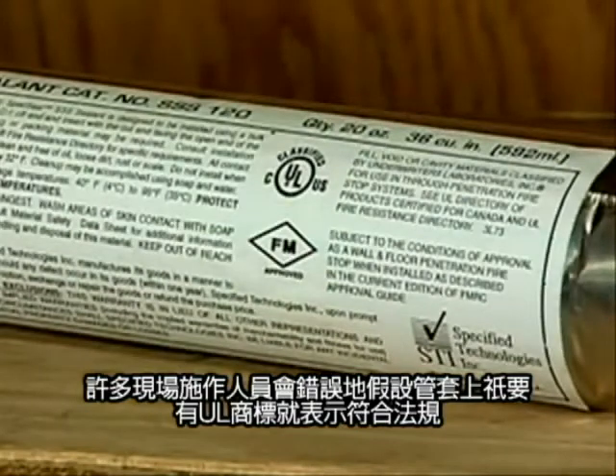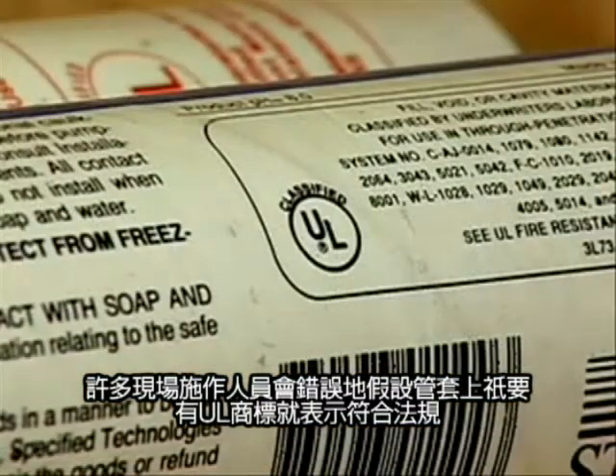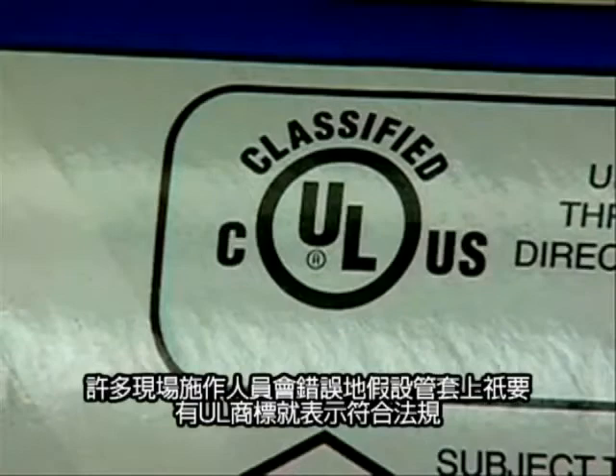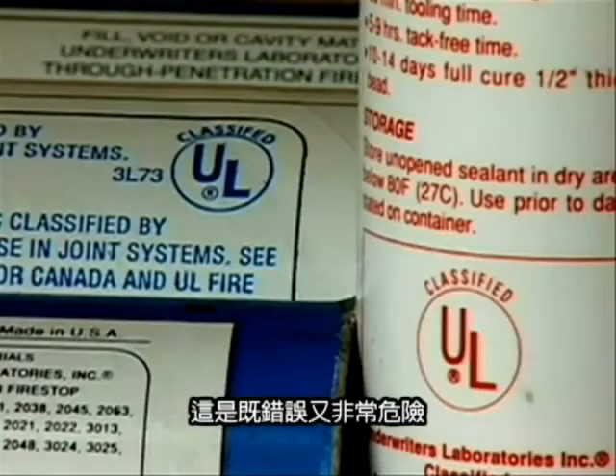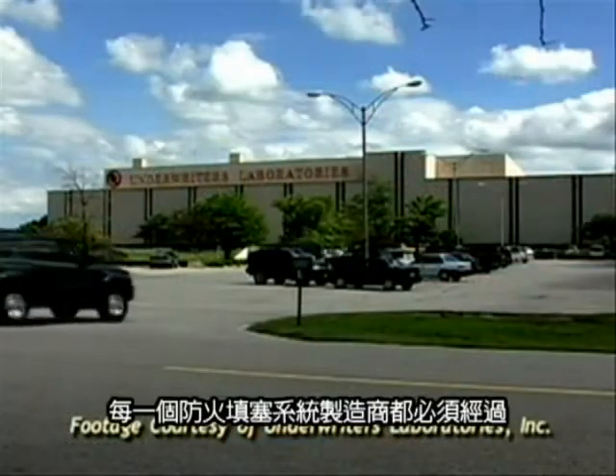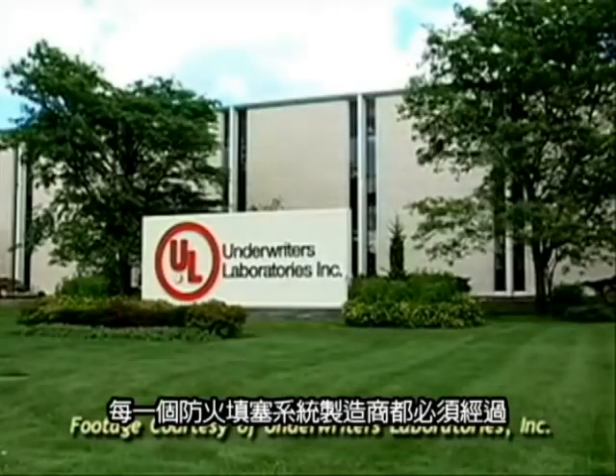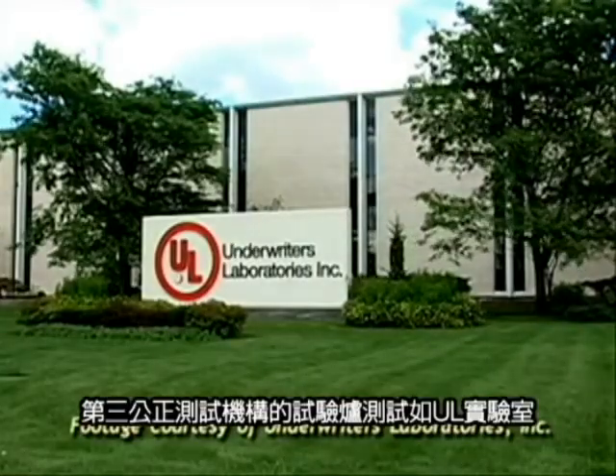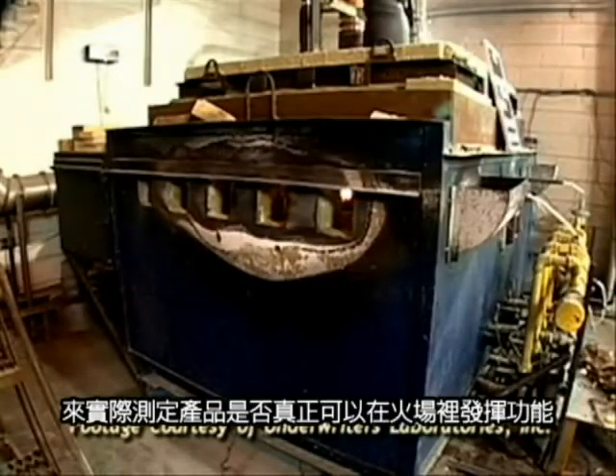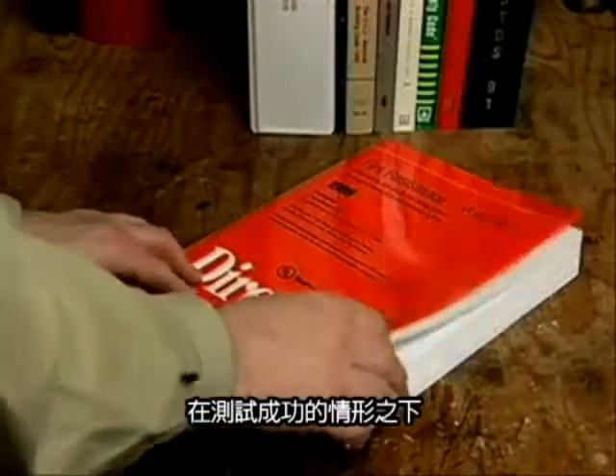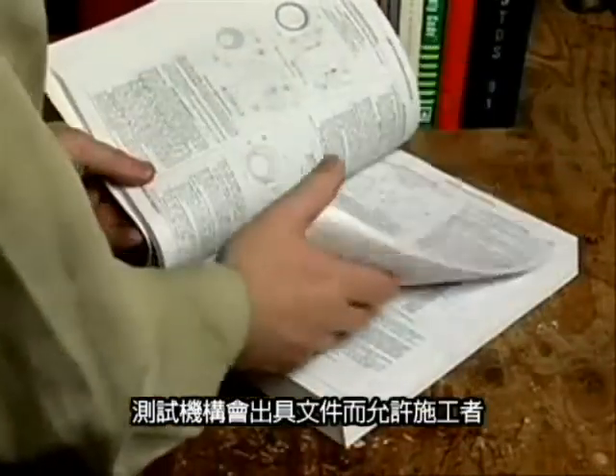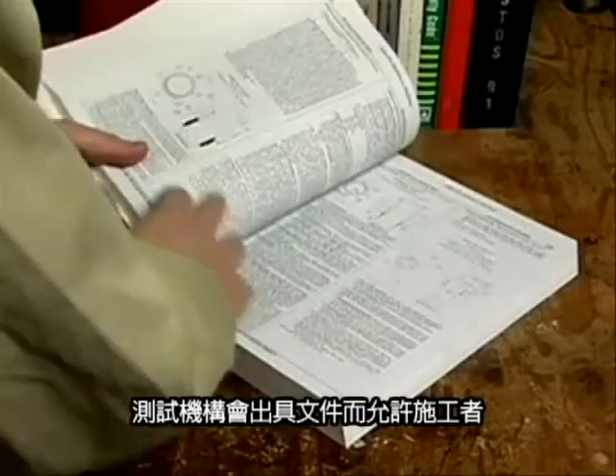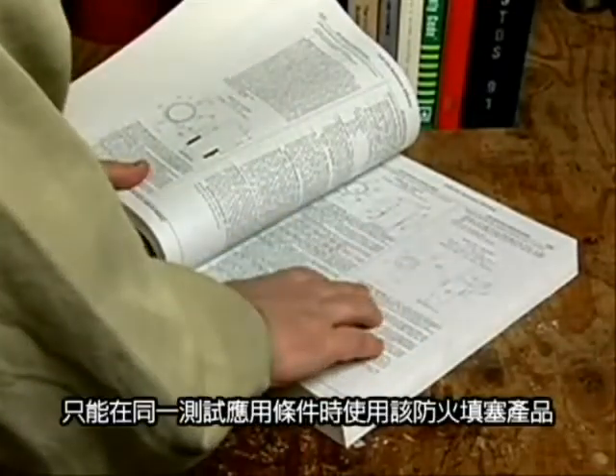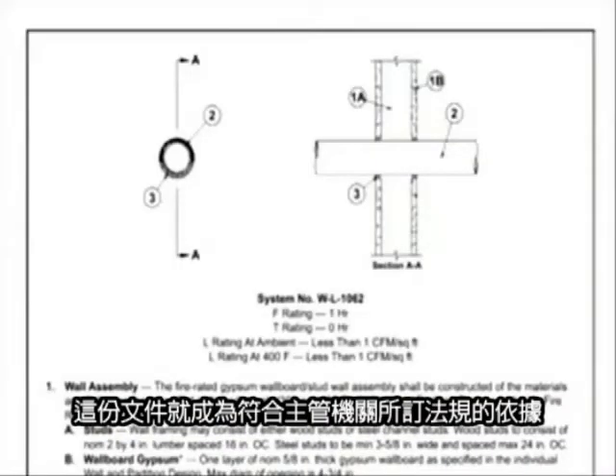Many installers mistakenly assume that simply having a UL logo on the tube offers adequate compliance. This misconception can be very dangerous. Each manufacturer of fire stop is required to test their products in a furnace at a third-party lab such as UL to determine if their products actually work in the presence of fire. When a test is successful, the lab issues documentation that permits an installer to use that material only in the application tested. This documentation becomes the evidence of compliance to an authority having jurisdiction.